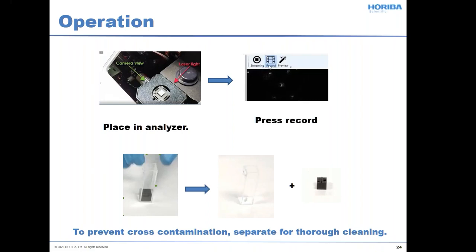Because we can take it apart and it's made of robust materials, we have a lot of cleaning options — soaking in bleach, using a water pick (which comes up more often with protein aggregates, which tend to be sticky, gooey messes), and ultrasonic baths. I mention cleaning so much because cross-contamination is an issue with these samples at very low particle concentrations. The cleaner your glassware, the better your results. If you have a system with dead spots, it's just not going to clean up well.